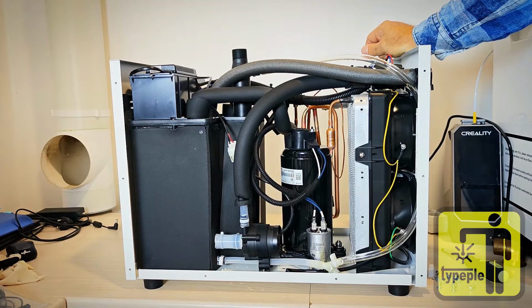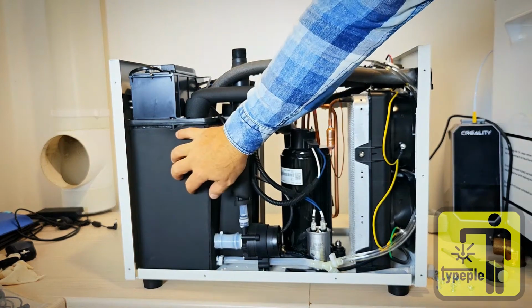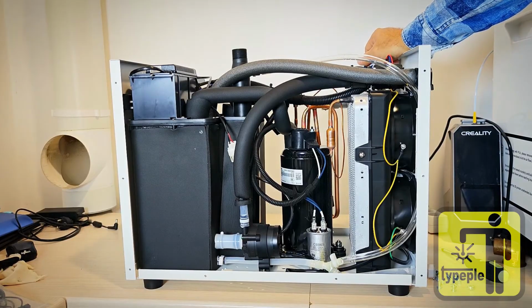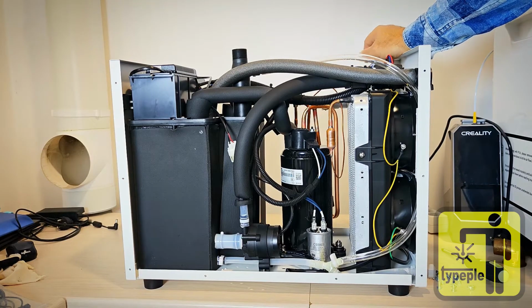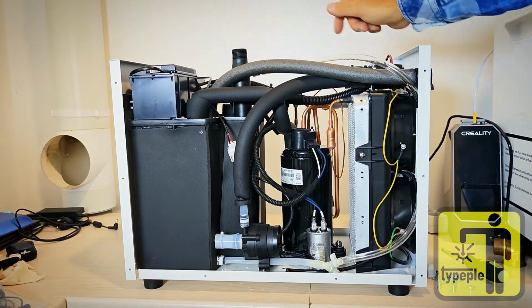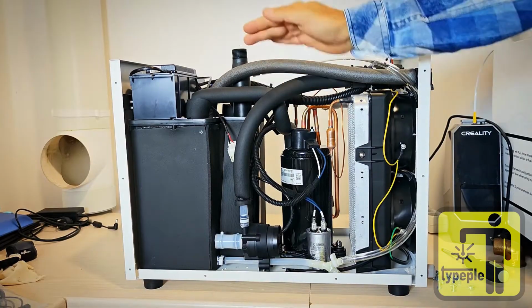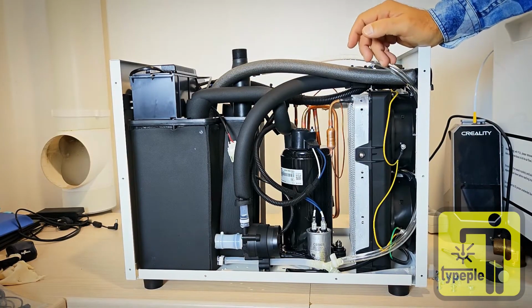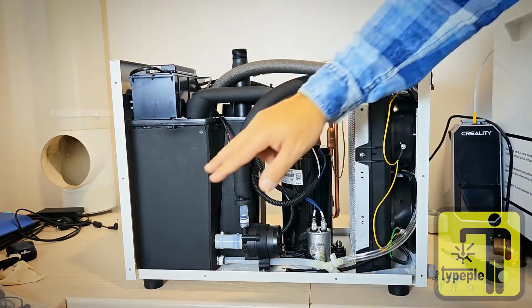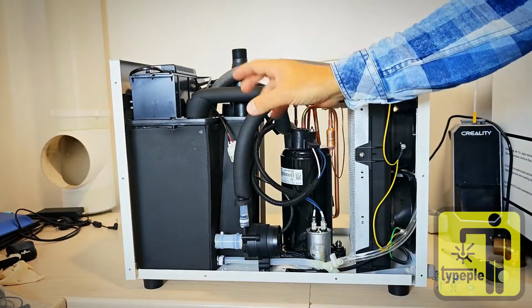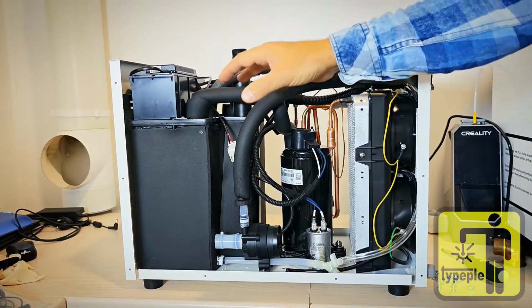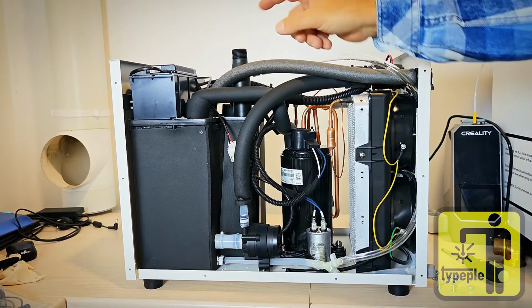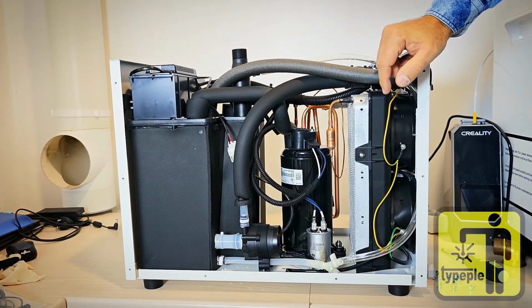Again, this provides both heating and cooling. Inside the tank itself there's a heating element that warms the water if the temperature drops below a set level, and it heats it up to whatever upper threshold we've configured. Then the compressor kicks in and starts working in the opposite direction, so the temperature is constantly fluctuating up and down. The advantage of having large tanks or reservoirs is that they act as a buffer, storing a specific temperature - this means any temperature drops or spikes, depending on how much your machine heats up, happen more gradually. So it really comes down to what kind of machine you're using and for what purpose.